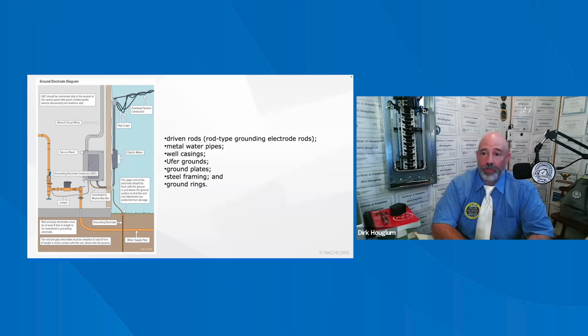Most residential construction requires two grounding electrodes in combination of the following, which need to be driven at least 6 feet apart. Driven grounding rods, that would be the rod type grounding electrode rods, the metal water pipes, metal well casings, Ufer grounds, those are going into the slab, grounding plates, steel framing, and grounding rings.